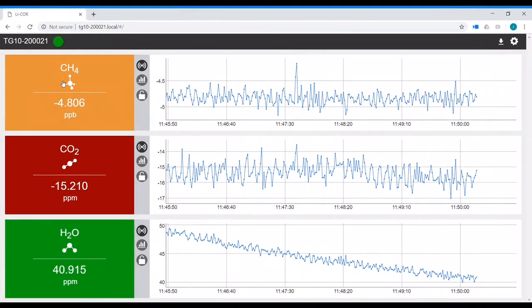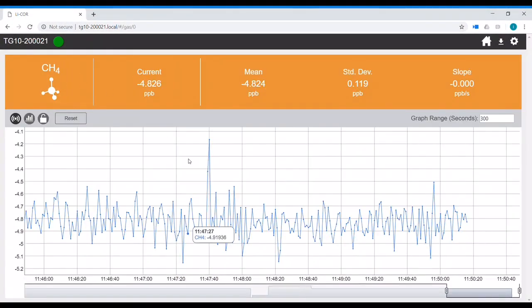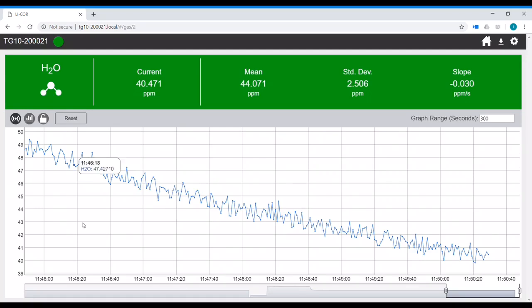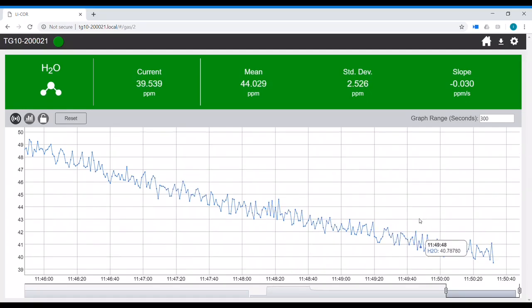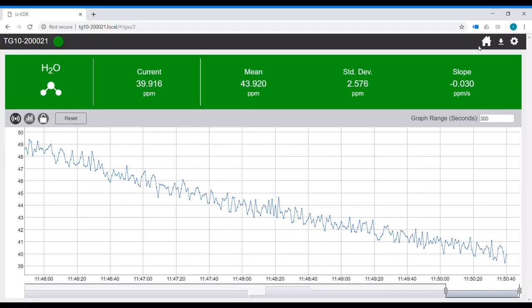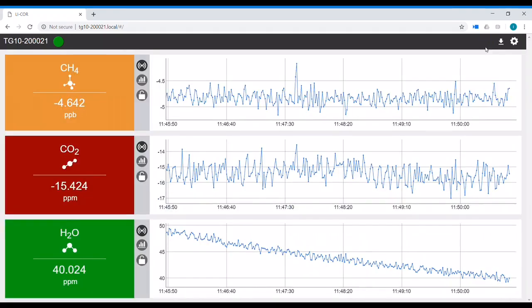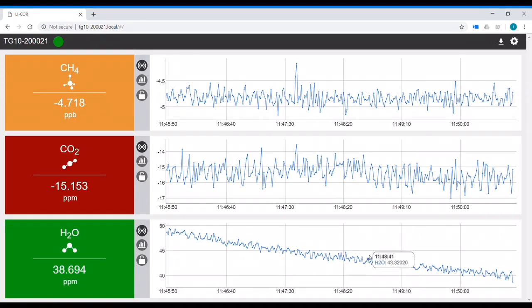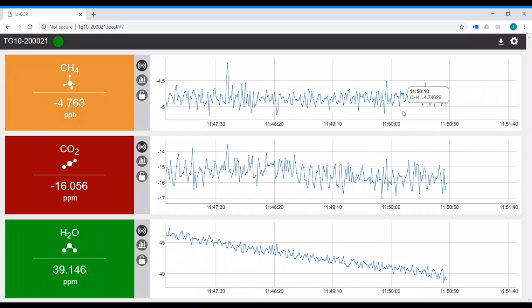So you can click on each gas to see further detail. You can see for the last 5 minutes the average value is here, and the slope is essentially zero for the last 5 minutes. So we need to look at water primarily. It's also trending down, but it's only trending down by a few ppm. This is in the noise of the instrument. So we're just going to wait until everything is stable. Water looks to be getting to a stable state, methane looks to be in a stable state, so we can go ahead and go to the calibration.